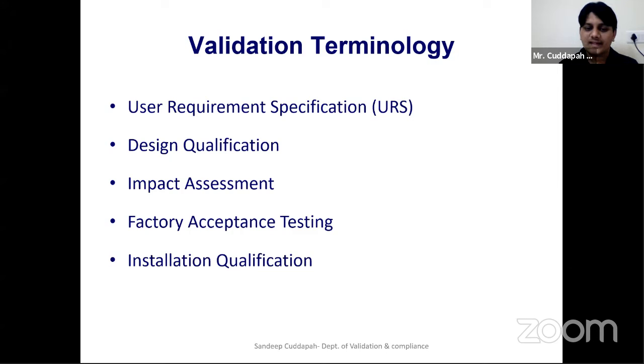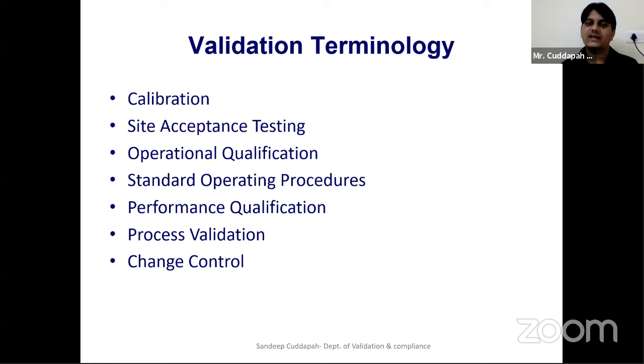Then once the equipment comes into the factory, you will do factory acceptance testing. Once the factory testing is done, the equipment will come to the actual installation location. There they call it the site acceptance test. Where you are installing the equipment, in those locations you will do this testing. Under the site acceptance test, your installation qualification and your operational qualification all come into the picture.